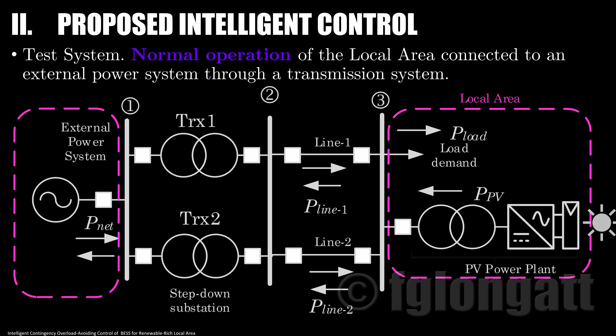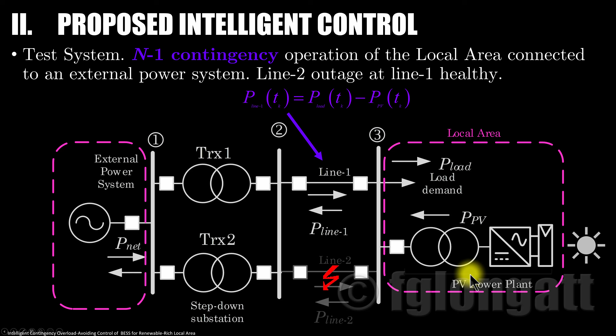The local area on the right-hand side is very rich in renewables, in this case photovoltaic power plants. Now, what happens if we have a single contingency at the transmission lines? Let's say there is a fault at transmission line number 2, and suddenly there is a disconnection. Between bus bar number 2 and number 3, we are left working with a single transmission line, and the total active power moving through that line will basically be the difference between the local power demand inside the PV-rich area and the time-dependent active power production of the PV power plant.